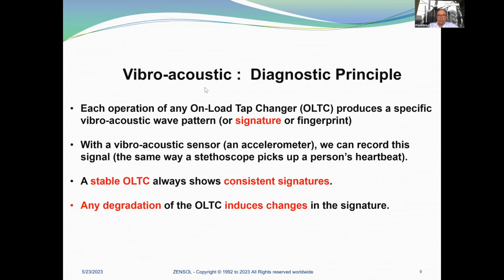So the diagnostic principle, what is it? Each operation of any on-load tap changer produces a specific vibroacoustic wave pattern, which we call a signature or a fingerprint. With a vibroacoustic sensor, which is an accelerometer, we can record the signal the same way a stethoscope picks up a person's heartbeat. A stable OLTC always shows consistent signatures, and any degradation of the OLTC induces a change in the signature.